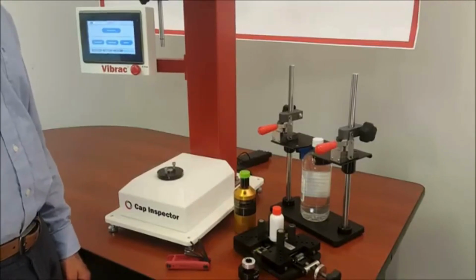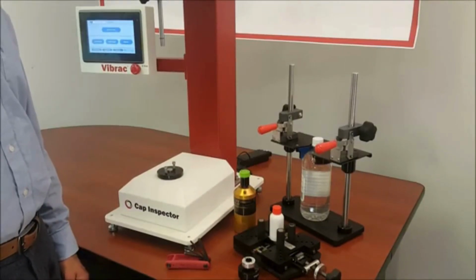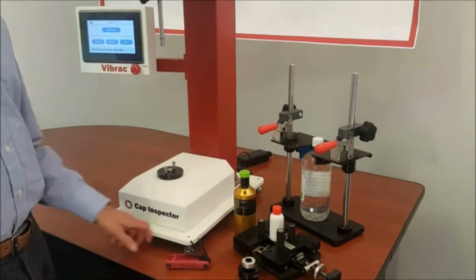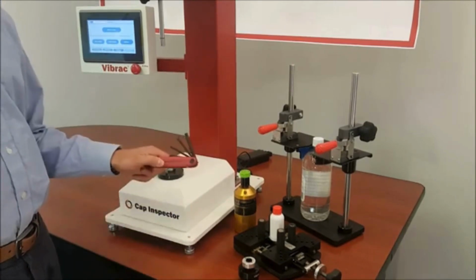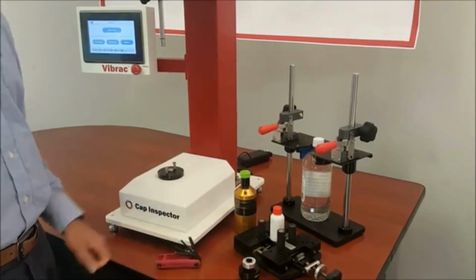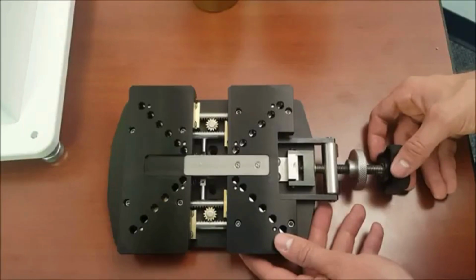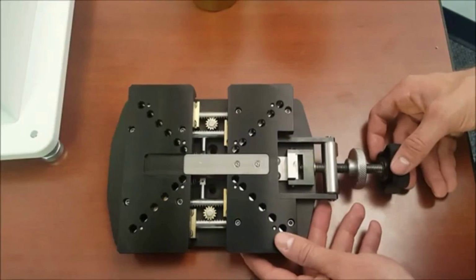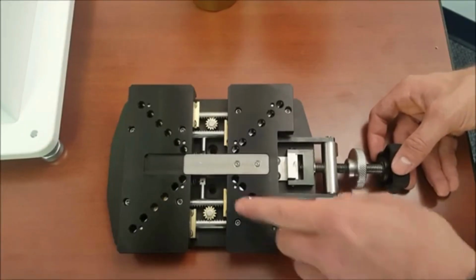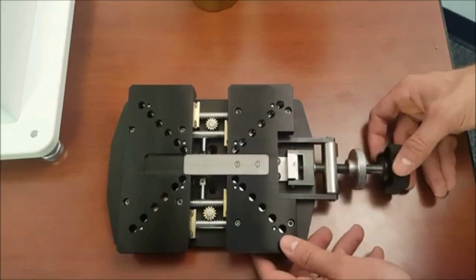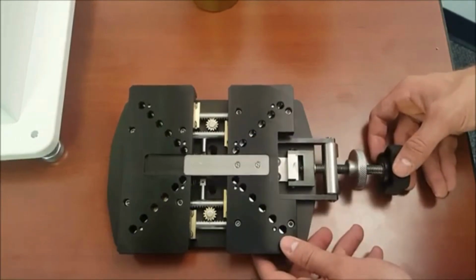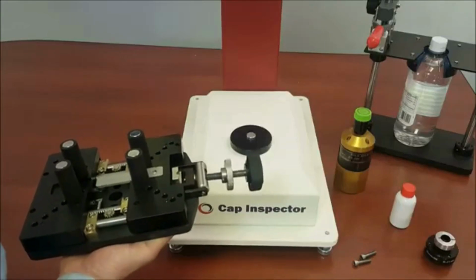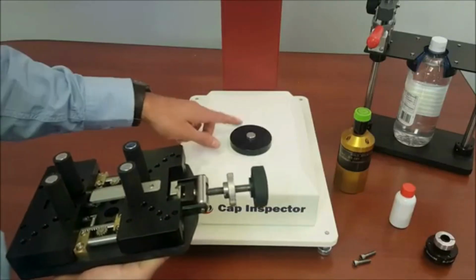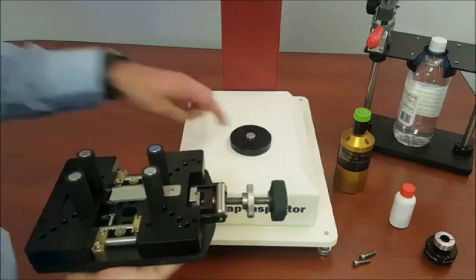Now we will cover how to properly set up your Cap Inspector for a test. You will need to provide a set of Allen wrenches to tighten the tooling to the Cap Inspector. When attaching, the bottle clamp will need to be open to the point where the screw holes are visible, so you may secure it to the torque shaft on the Cap Inspector. To attach, fit the bottle clamp on the torque shaft and align the screw holes.